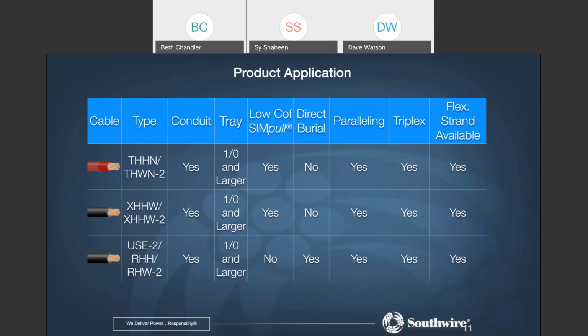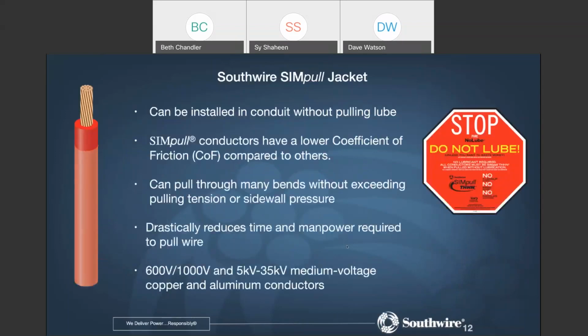In terms of direct burial rating, you'll see that the THHN and XHHW are not rated for direct burial, but the USE rating on the triple rated product allows it to be installed with direct burial. Now we can do paralleling and triplex, and we also have this flexible strand available for all of these constructions. Paralleling is where the product will arrive on one reel with all of the conductor colors that you need, all of your phase conductors.